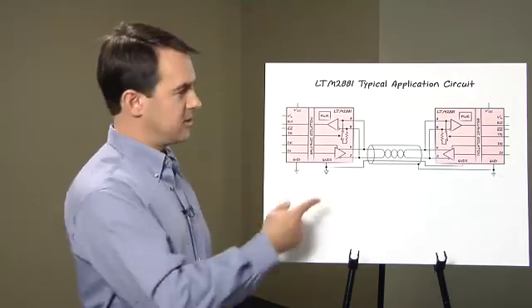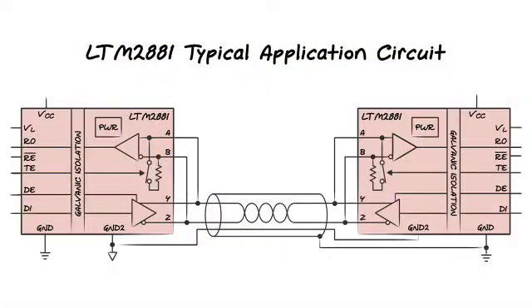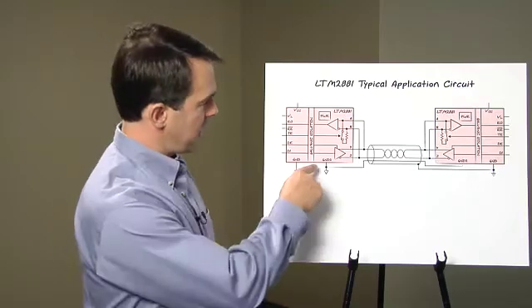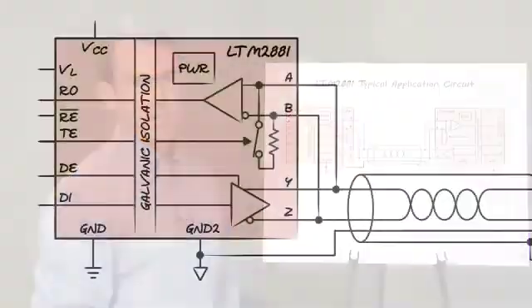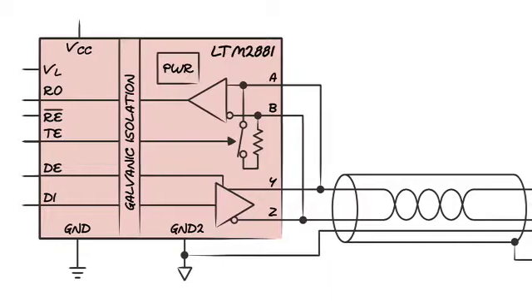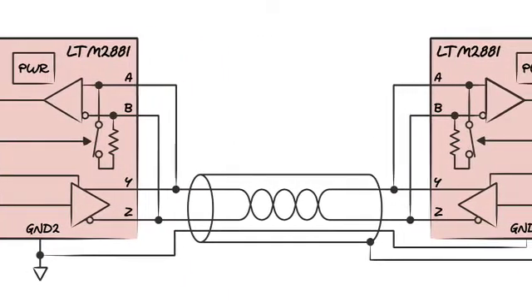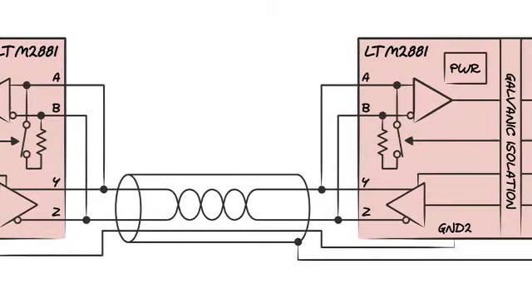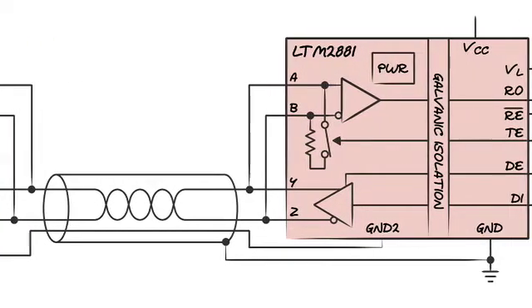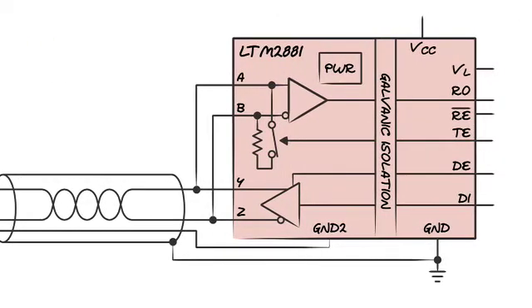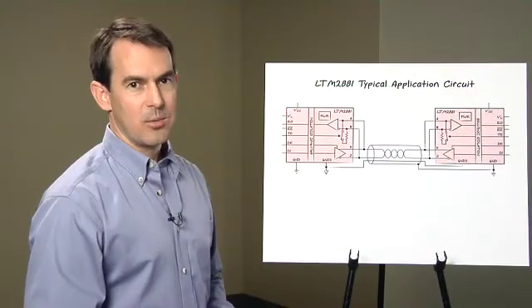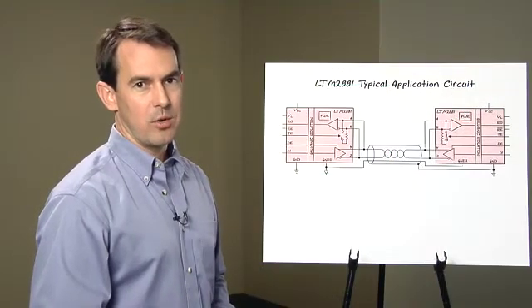Finally, here's the simplified LTM 2881 application circuit. One important consideration is proper wiring of isolated transceiver networks. Each isolated transceiver common, ground 2 shown here on each unit, should be connected to a common wire or the cable shield. This forces common mode voltage and noise to be absorbed and rejected by the isolation barrier instead of appearing directly across the RS-485 receiver inputs.